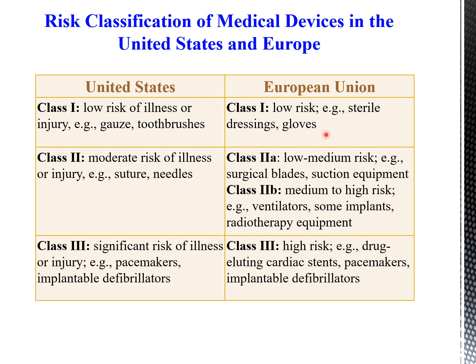Coming to Class 1 in Europe, low risk, examples are sterile dressings and gloves. Class 2A means low to medium risk, for example, surgical blades, suction equipment. Class 2B means medium to high risk, ventilators, some implants, radiotherapy equipment, etc. Finally, Class 3 means drug-eluting cardiac stents, pacemakers, implantable defibrillators. They come under Class 3 according to the European Union.